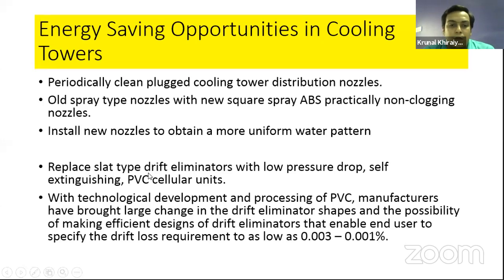Then the next, very important, is drift. For reduction in evaporation losses, you need to replace the slat type drift eliminator with a low pressure drop type. Meaning the pressure drops are also low. If you are changing the design of these eliminators, it affects the pressure drop, so keep in mind that low pressure drops are needed, and you need to replace the drift eliminators. With technological development and the processing of PVC, manufacturing has brought large changes in drift eliminator shape and the possibility to make efficient designs.